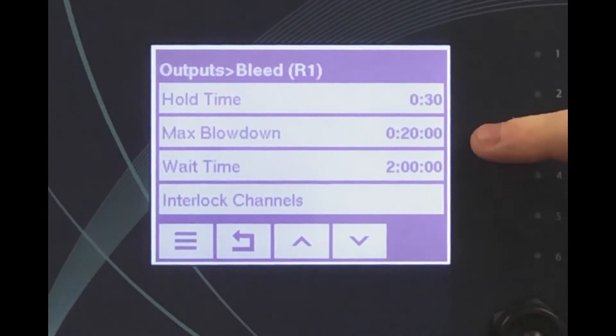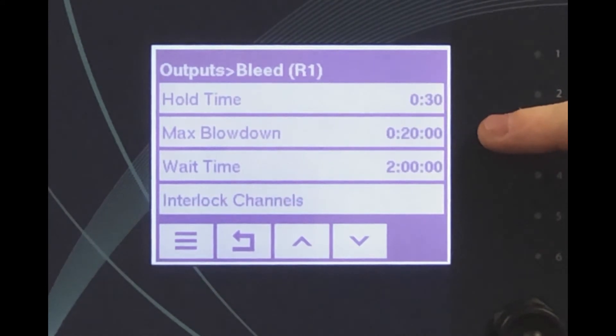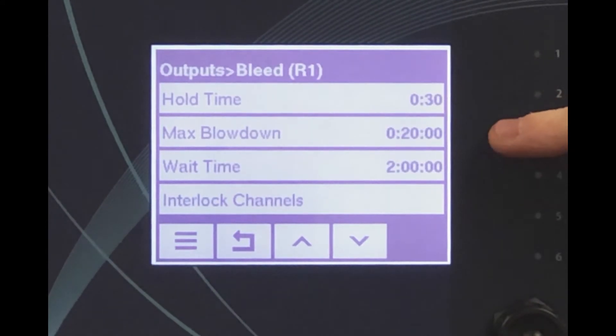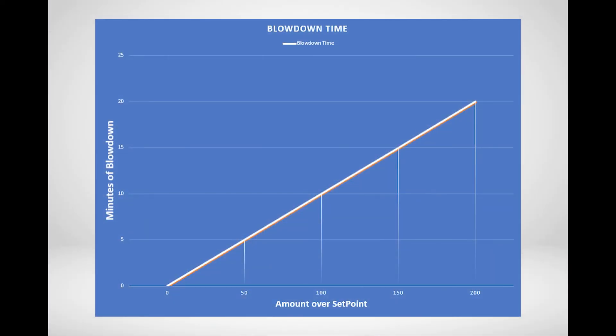With the settings shown here, if the conductivity is 200 microsiemens or more over the set point, the boiler will blow down for 20 minutes before trapping and reading the sample again. If it is only 100 microsiemens over the set point, the controller will blow down for only 10 minutes before trapping and reading again. The controller calculates the percentage of the proportional band and uses that percentage of the maximum blowdown time to determine how long the blowdown valve should be open.